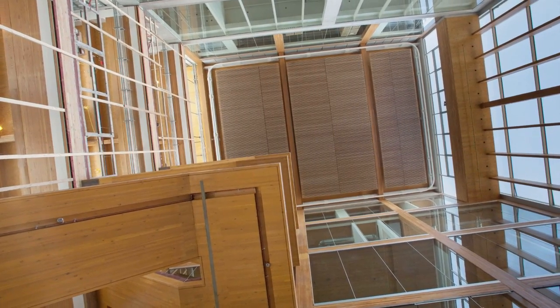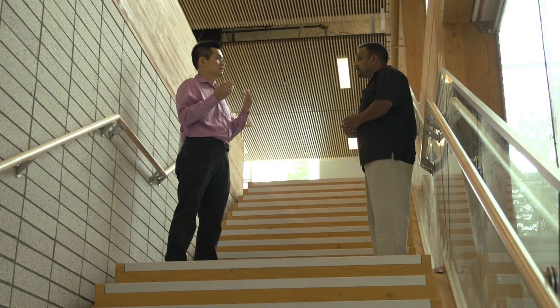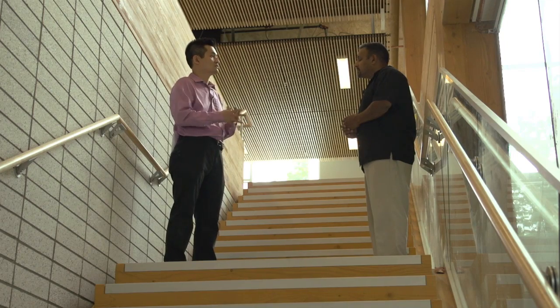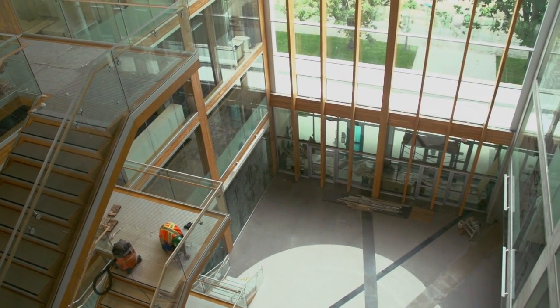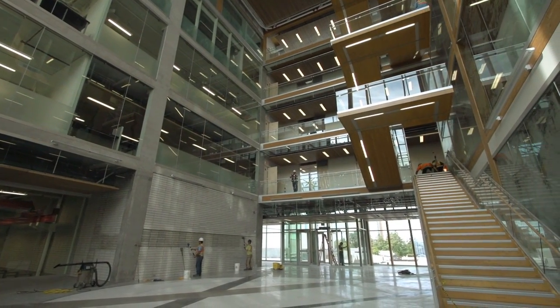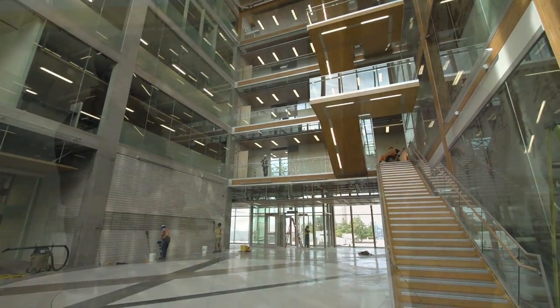The analysis essentially involved looking at how the building will perform in fire and how the resultant impact will affect the occupants in the building itself. This is very much similar to structural engineering design, where structural engineers look at seismic, gravity, and wind forces. We, as fire engineers, look at the fire forces. The fire scenarios we looked at in our analysis were based on theories of compartment fire dynamics, and it is the same test we look at for non-combustible buildings such as steel and concrete.